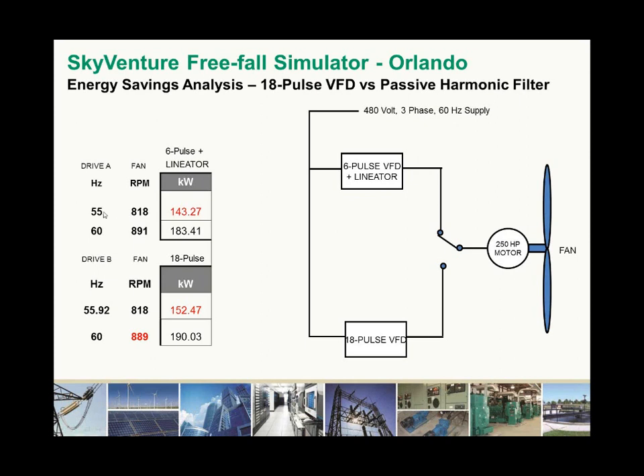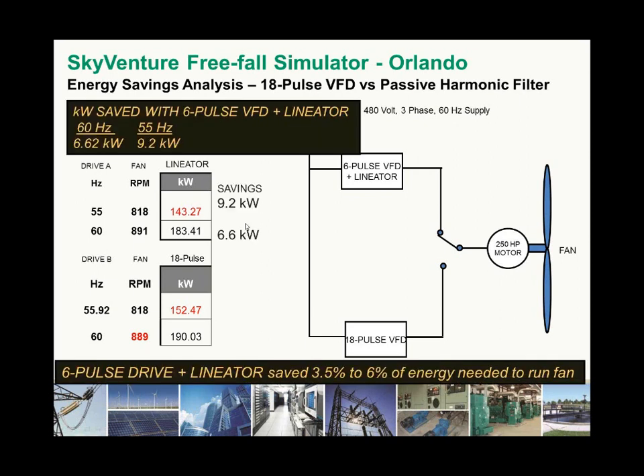The 55 hertz, we could get to it with the Lineator filter in the drive at a lower speed on the drive, which reduced the energy consumption even further. So we had 143 kilowatts. So in this case, when we were running at 60 hertz, the net savings was 3.5%, and when we're running at 55 or 56 hertz to get the 818 RPM fan speed, the energy savings was 6%. So it's much more substantial reduction.